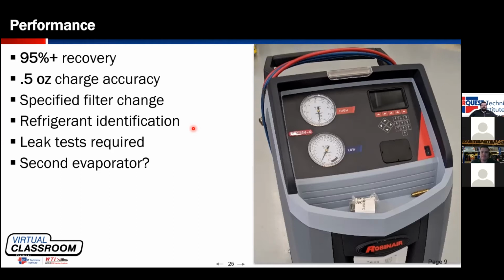And there are a couple of ways that the manufacturers are doing this with the equipment. One is the scales are better. The scales also, you can see it sitting in the tray of the machine here. It came with a calibration weight so that we can periodically check the accuracy of the scale that is inside this machine. Set the calibration weight, it is a known weight, and look at the weight increase on the display to see if our scale is accurate. When we are charging the refrigerant, you always would have some refrigerant left inside the machine. There's in the internal plumbing, in the hoses.